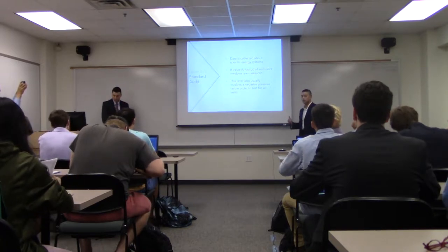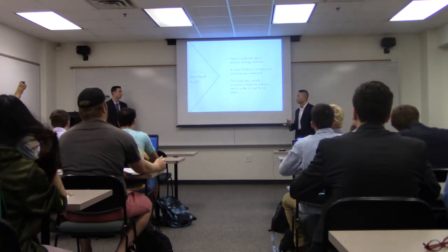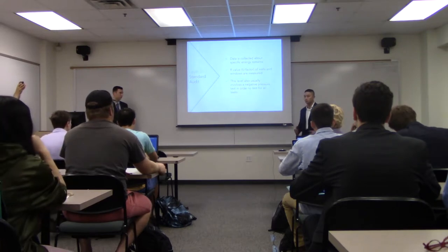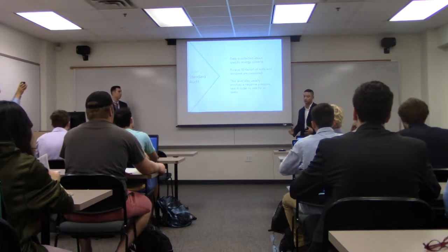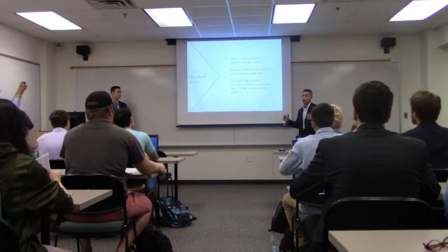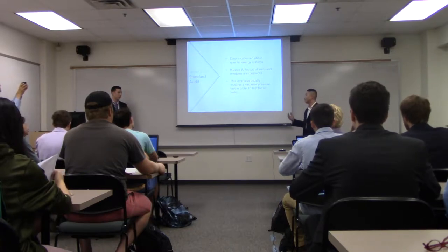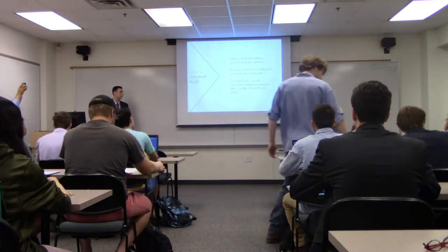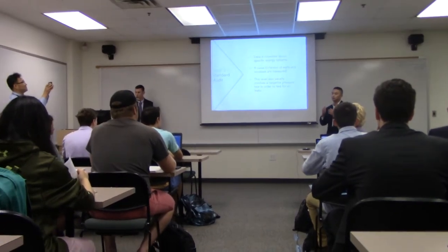The last part of this step that we didn't get to do is the negative pressure test. The reason we weren't able to do it is because the building was so big. To give you an idea of what it is: you take a big fan, stick it at the front door, seal the whole building off, and turn on the fan so it sucks all the air out. The building becomes negatively pressurized, and then you can go in with a thermal camera — since it's under negative pressure, air will rush in through leaks and you'll be able to identify them because there'll be a temperature difference.